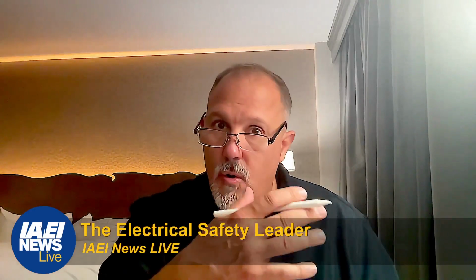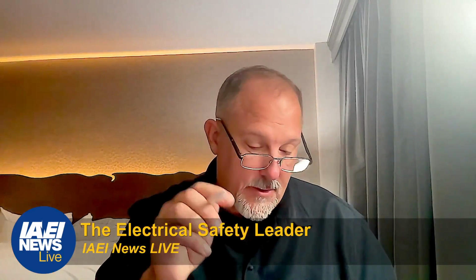And they put like a saline solution, they add some stuff in there. But in any case, there's a difference between those two, whether the receptacle assembly is for a work surface or a countertop. And that's a little detail. So that's how we addressed the countertops, etc. So in the 2023, we made it optional, which will probably mean you're not going to see a lot of receptacles in those areas.